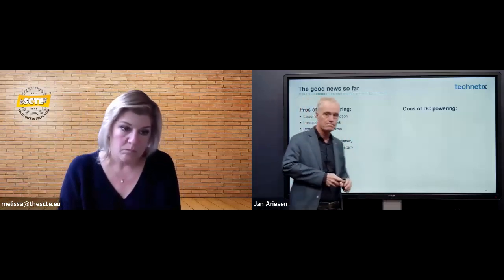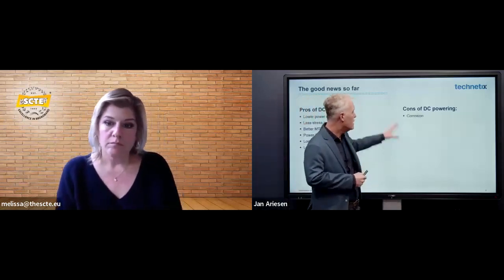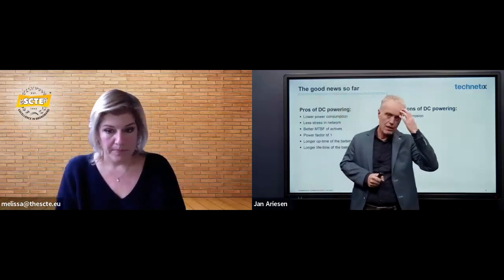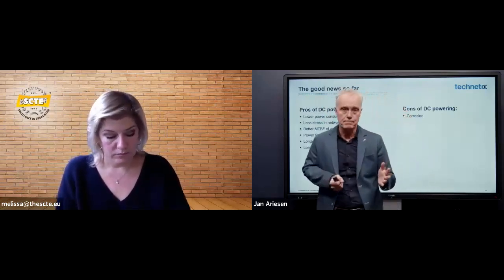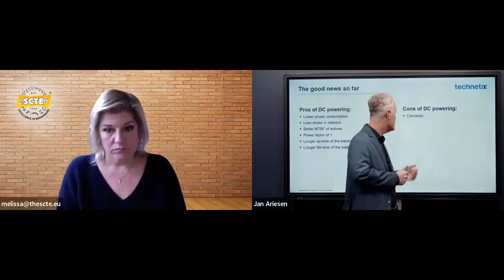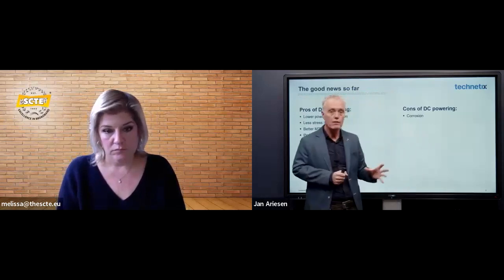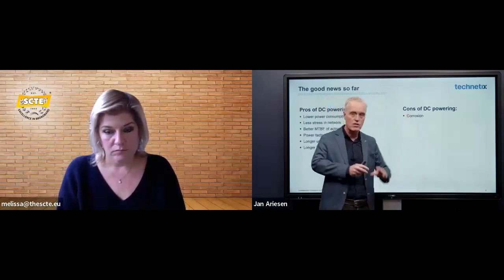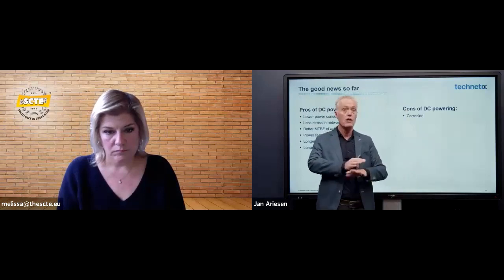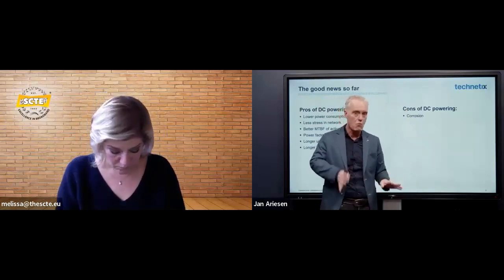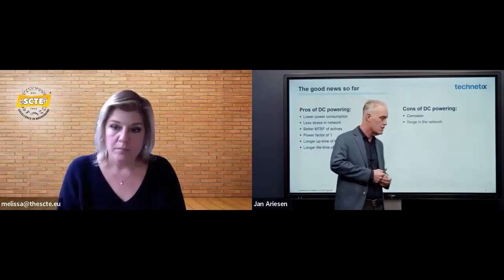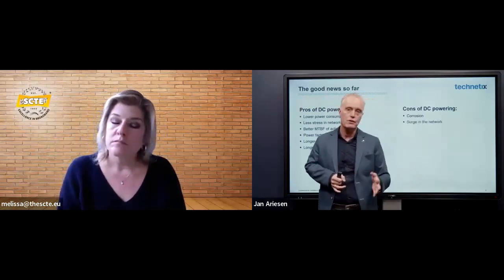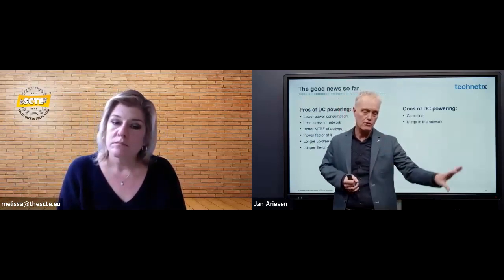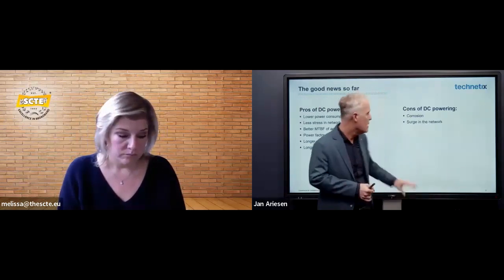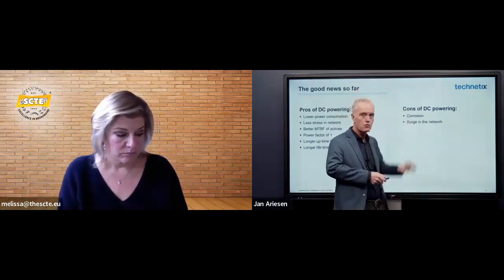Now the cons of DC powering. DC powering causes corrosion, which I'll explain in a few slides - it's an important part, and one of the reasons DC powering has never been used before, because nobody wants corrosion in the network. The other issue is surge in the network - not surge to the transformer, but surge in the network itself. I want to explain both parts.